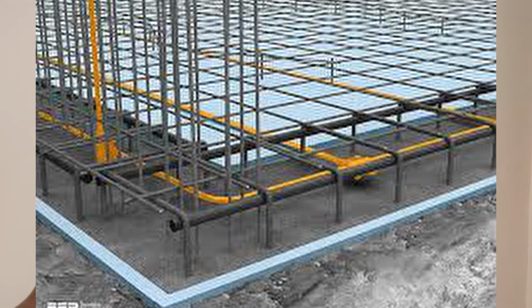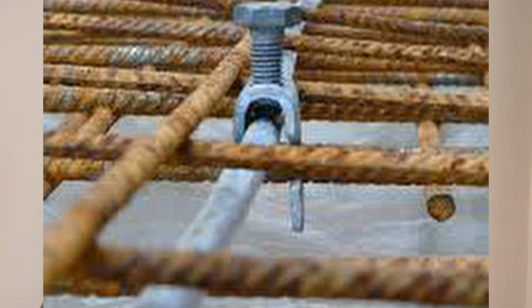The best earthing system is installed before concrete is poured. You can integrate the earthing with the structural reinforcement bars, the rods, on the foundation before the concrete is poured. That's the most effective, solid earthing system, because you're using the steel reinforcement bars to form part of your earthing and lightning protection system. That is the best, and that is what we call foundation earthing, or ring earthing.